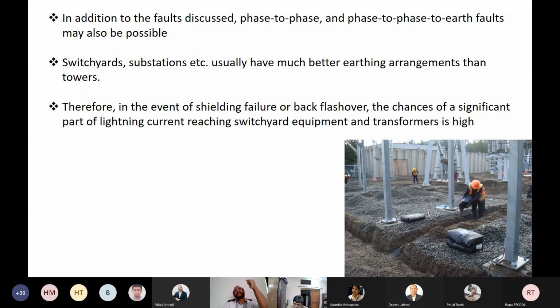There may be a chance that a flashover happens from a phase at the top to a phase at the bottom in a multiple line scenario, then from that bottom phase to the ground, or if there is a neutral wire, in the case of the lines coming from a star configuration, there may be a flashover to the neutral. Then switchyards, substations, etc. usually have much better earthing arrangements than towers. So I'm sure that you can understand about it.